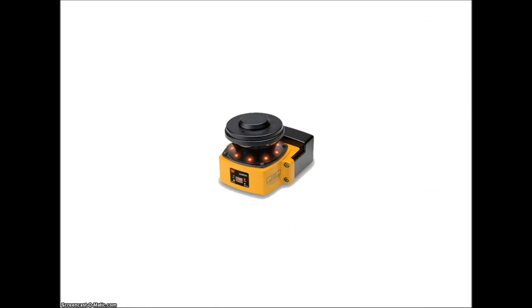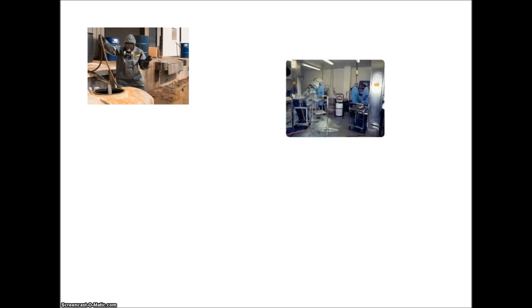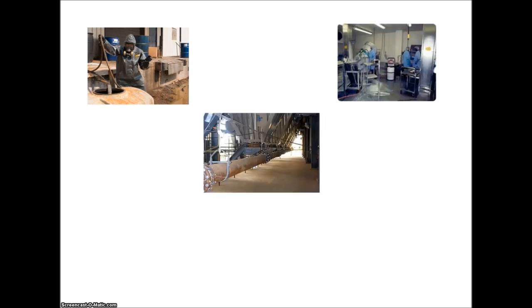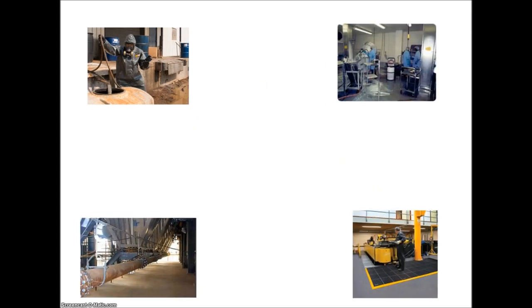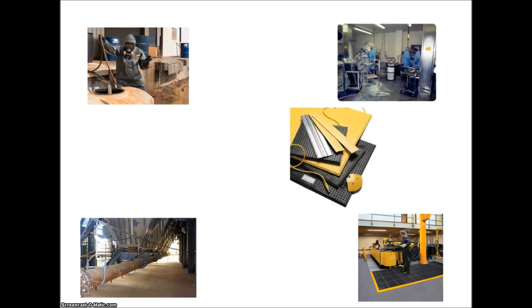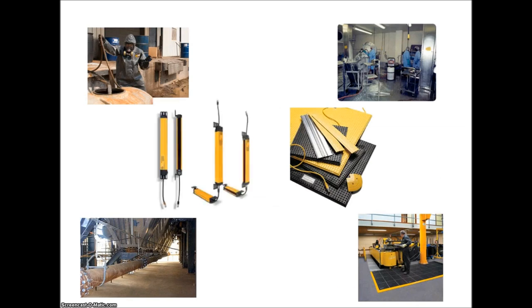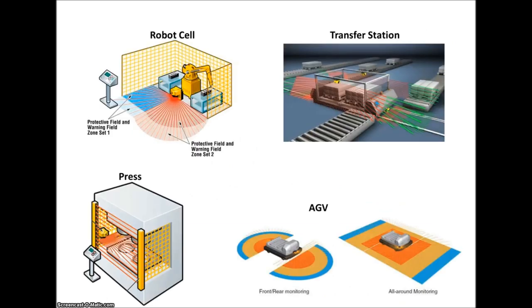A safety laser scanner may not always be the best choice in a safety application. In a dirty or wet environment, direct sunlight, or a small scan area, it's better to go with a safety mat. In a vertical application, we typically recommend safety light curtains. The laser scanner is a great choice for robot cells, transfer stations, loading stations, presses, automatic guided vehicles, or anything requiring scan zone variation.